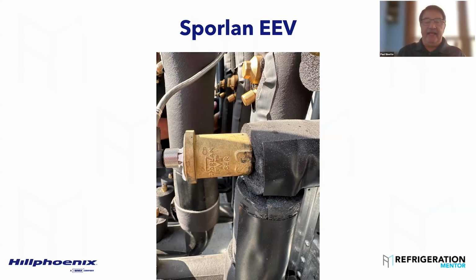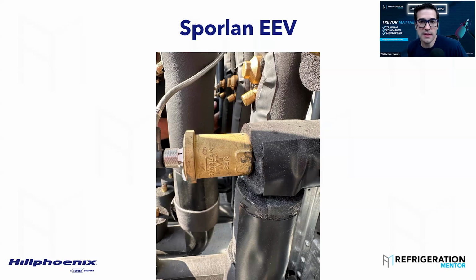Yep. Next thing, if you have ESRs on the system, you need to make sure that they're functioning and they're actually turning in the right direction before you go putting gas to your system. We don't use a lot of ESRs because with the new electronic controls, you can control your cases on multiple suction pressures. And that's a big thing. If you cross one of the wires across to one of the controllers, when it thinks it's closing, it's actually open, and vice versa. And this has nothing to do with CO2. This is just any electronic valve. So this is very important on startup. Exactly.